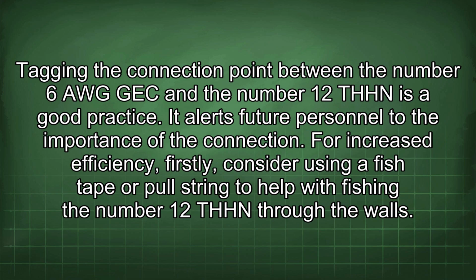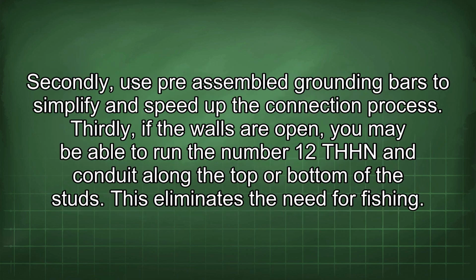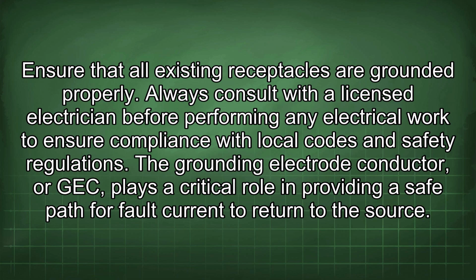For increased efficiency, firstly, consider using a fish tape or pull string to help with fishing the number 12 THHN through the walls. Secondly, use pre-assembled grounding bars to simplify and speed up the connection process. Thirdly, if the walls are open, you may be able to run the number 12 THHN and conduit along the top or bottom of the studs. This eliminates the need for fishing. Ensure that all existing receptacles are grounded properly. Always consult with a licensed electrician before performing any electrical work to ensure compliance with local codes and safety regulations.